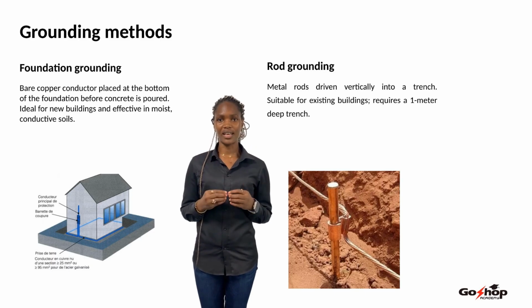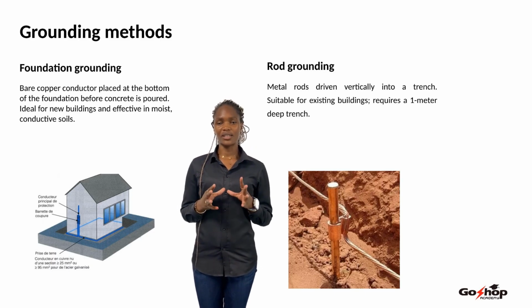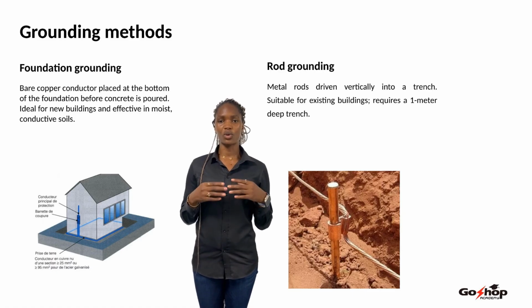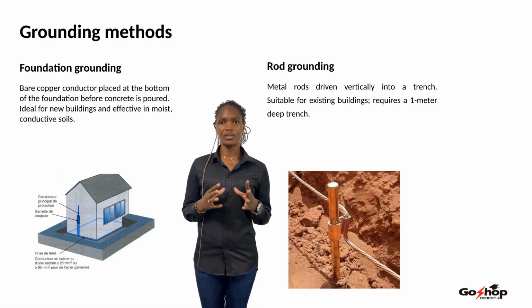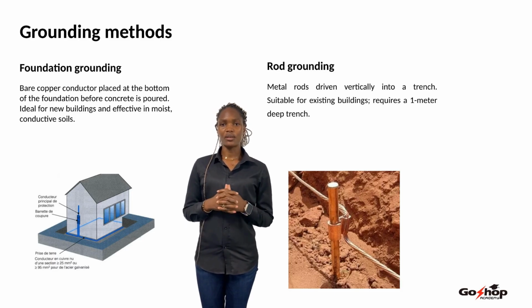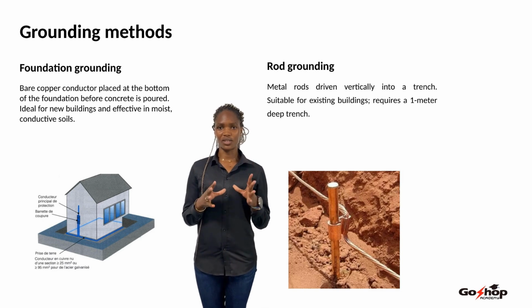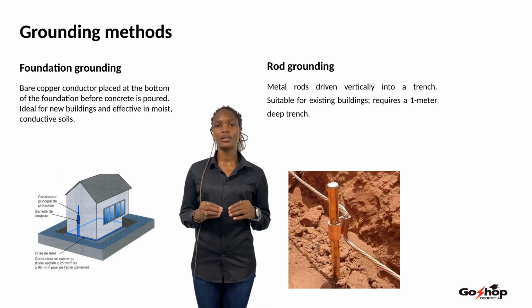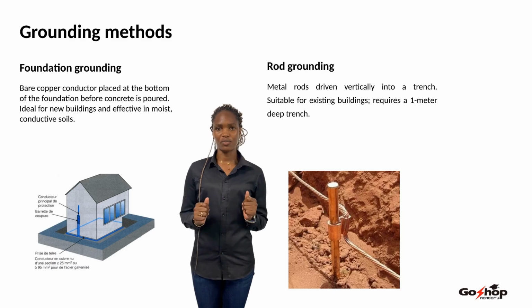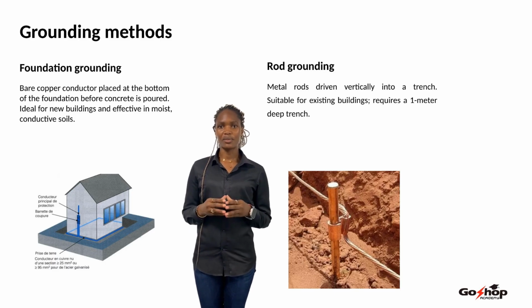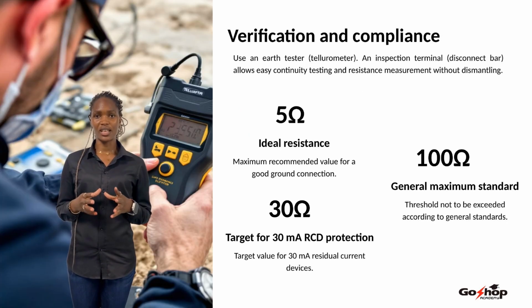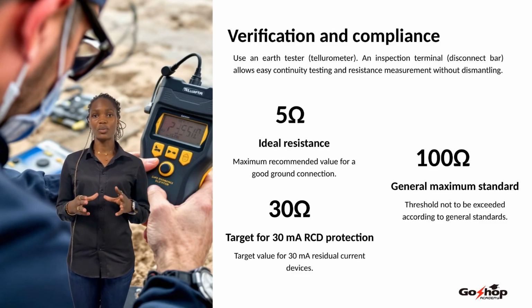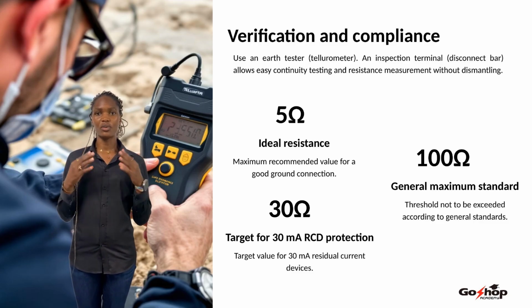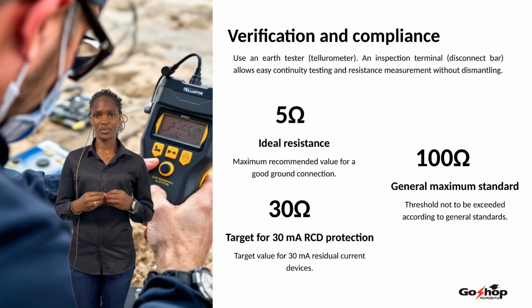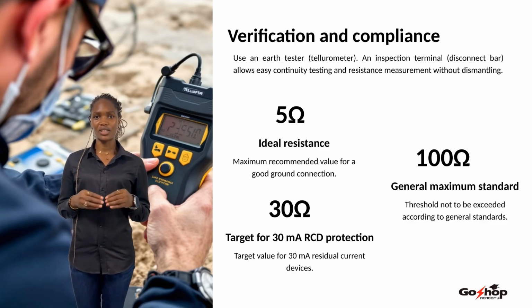Foundation grounding. A bare copper conductor is placed at the bottom of the foundation before concrete is poured. Ideal for new constructions and effective in moist, conductive soils. Rod grounding. Metal rods are driven into a trench. Suitable for existing buildings. Requires a trench about 1 meter deep. Verification is done using a ground resistance meter, tellurometer. A disconnect bar allows for continuity checks and resistance measurements without dismantling the installation.